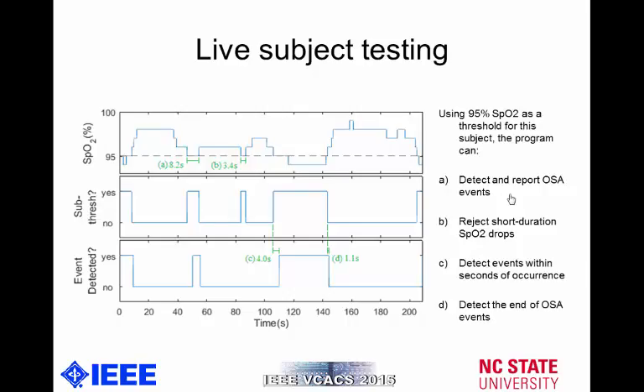How do we know the functionality is there? Because we tested it with a live subject. What we have in this figure is information from a test subject who we attached an artificially high threshold to. The top graph shows the patient's SpO2 data, which we had them manipulate by breathing in a particular way. The middle graph shows our threshold flag, determining whether or not the SpO2 values were at or below that threshold for what might be an apnea event. The bottom graph shows whether or not the information had been below the threshold long enough to actually be an apnea event — so the bottom graph is what actually shows if an apnea event is occurring or not.